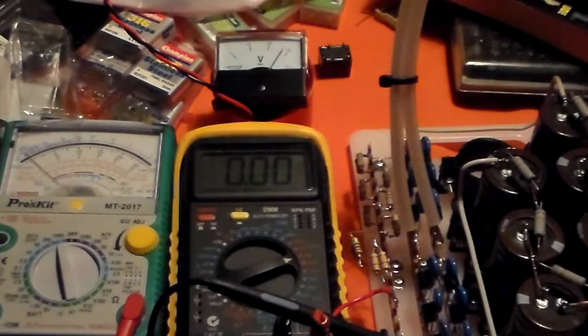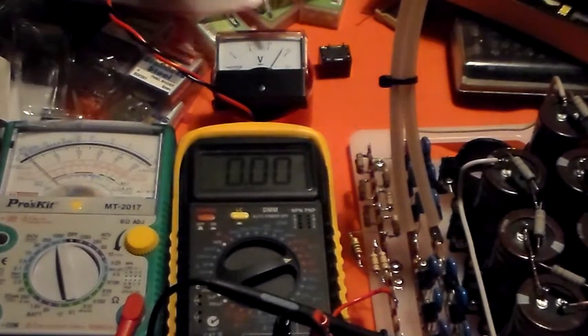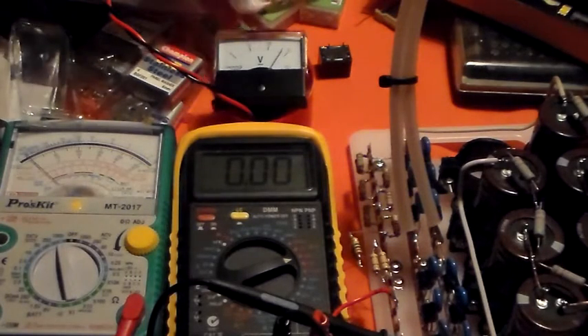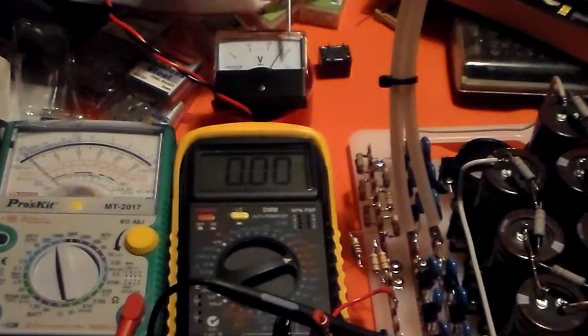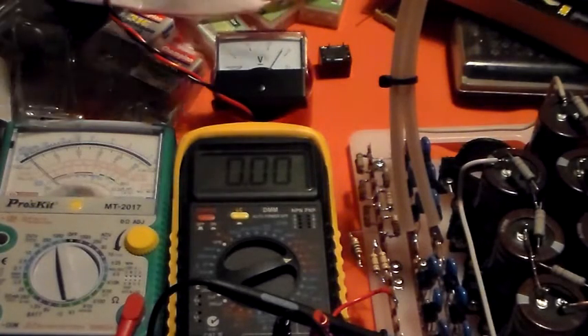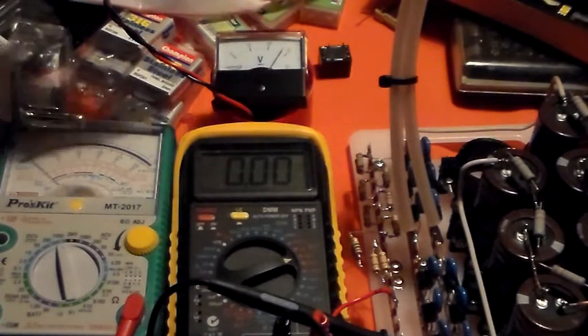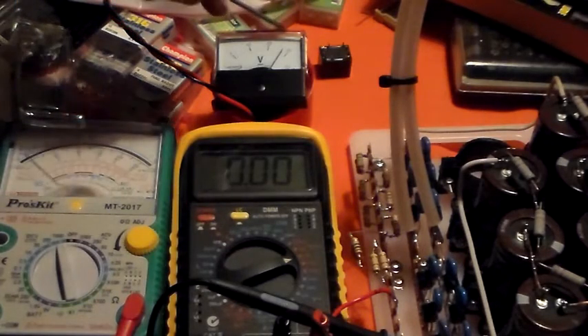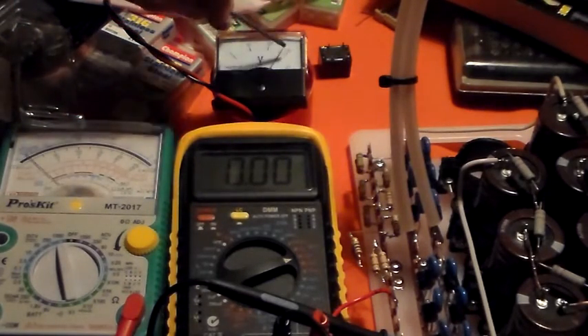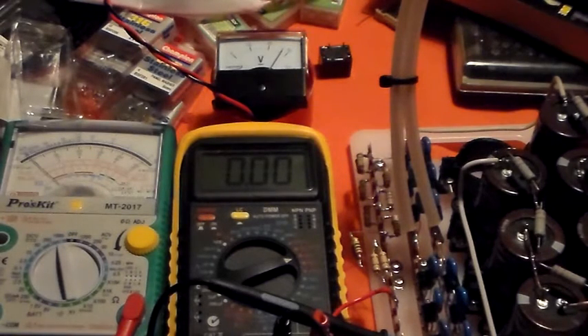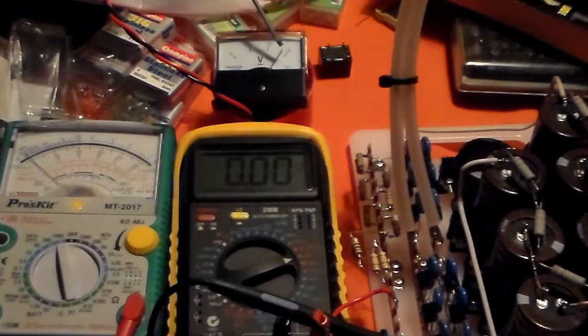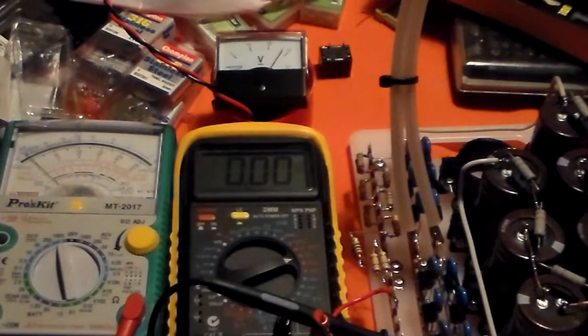Okay, so that being the case, this needle here should be just below the 30. So 2800 volts is that line just to the right of that needle. 2950 should be almost on that line by the 30 there. So where I'm interested in this meter being accurate, it's not accurate. It's not too bad at 1000 volts, but when we get up to the 3000 volt end, it's not too flash at all.